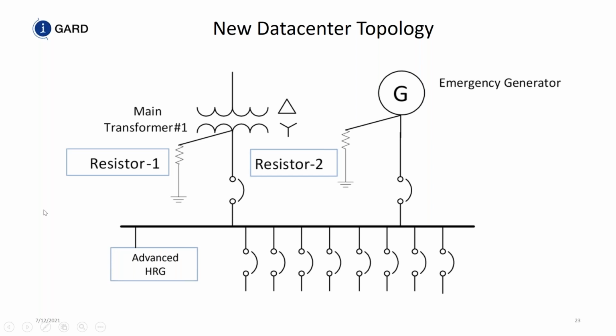pulsing. Now the pulsing, we can control both of these resistors, but only one of them is actually going to change because it's the one that's connected to your load. And so we feel this is a safer method of determining whether there's a fault on the system, because your operators are going to be looking at one HRG system to determine if there's a fault. They don't need to consider whether they're on generator or whether they're on utility. The fault is going to be in the load most of the time.